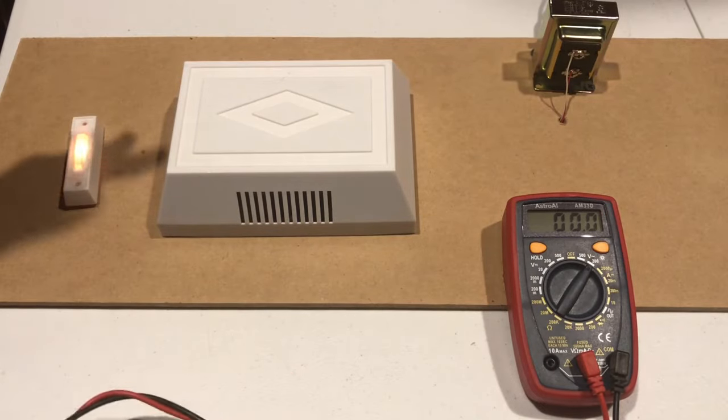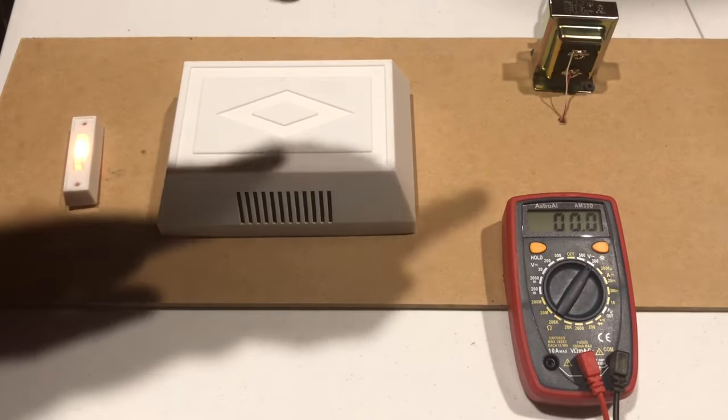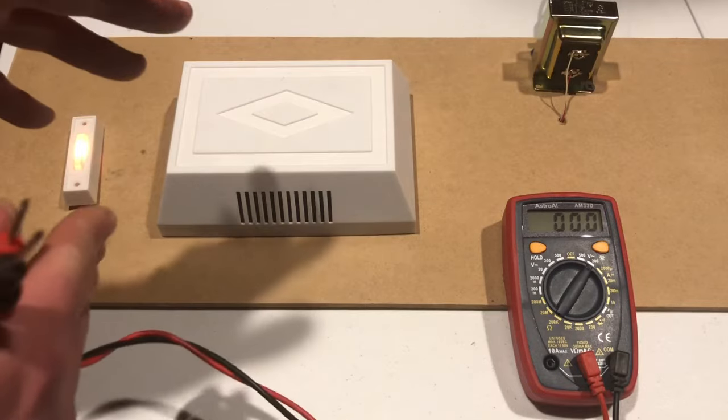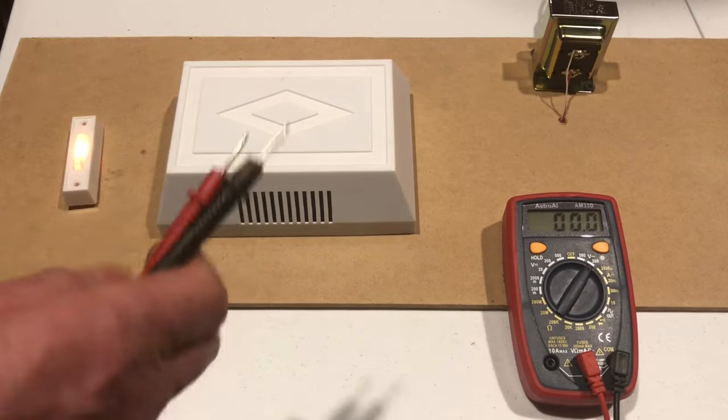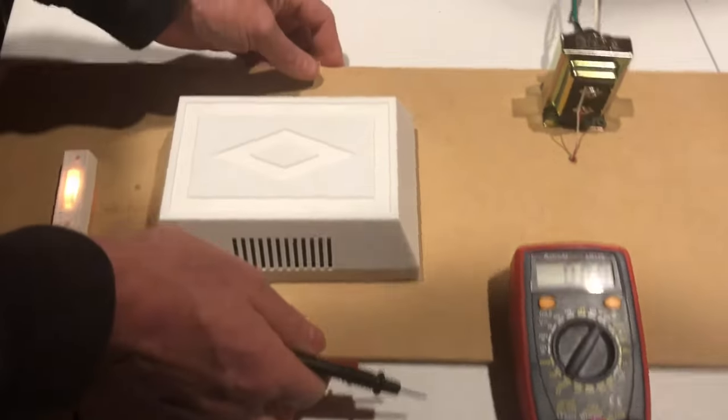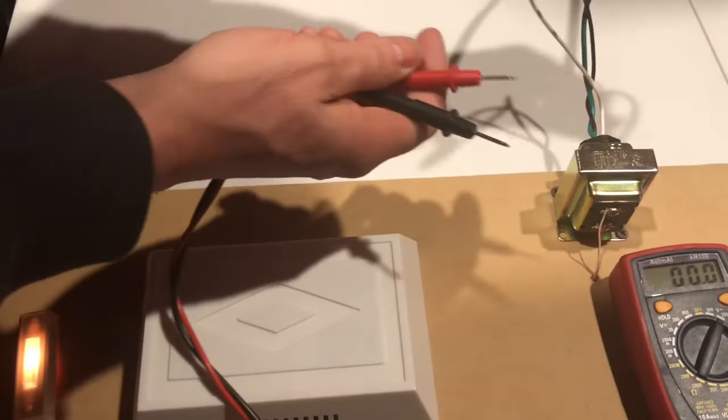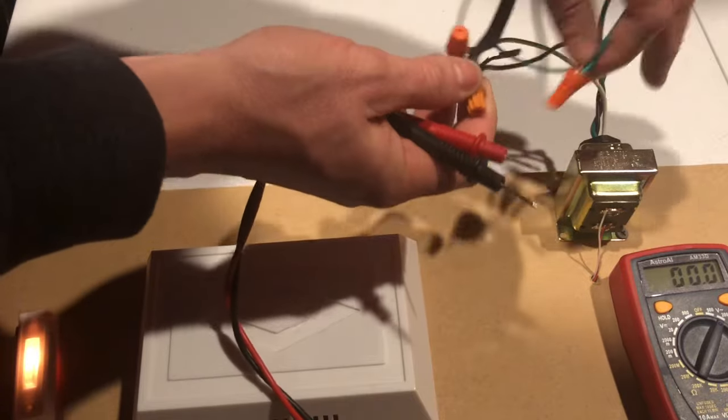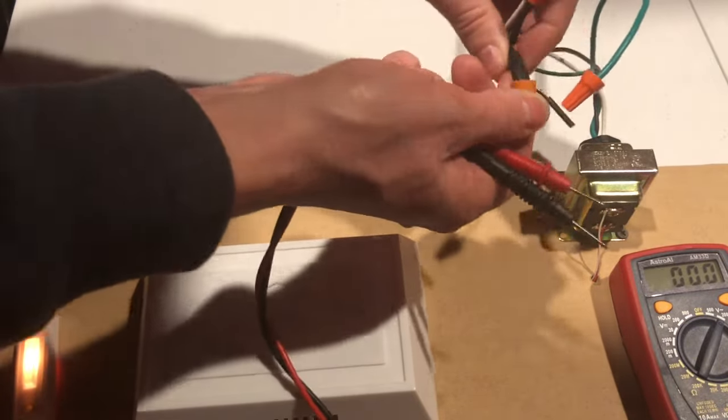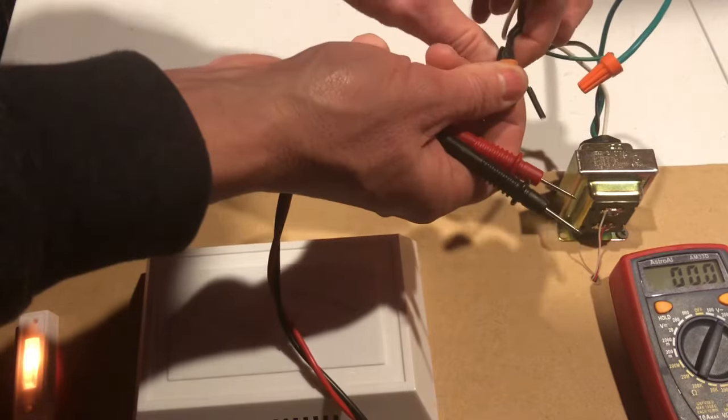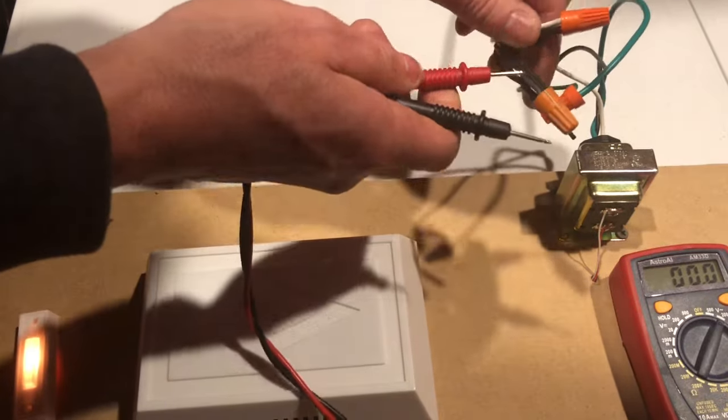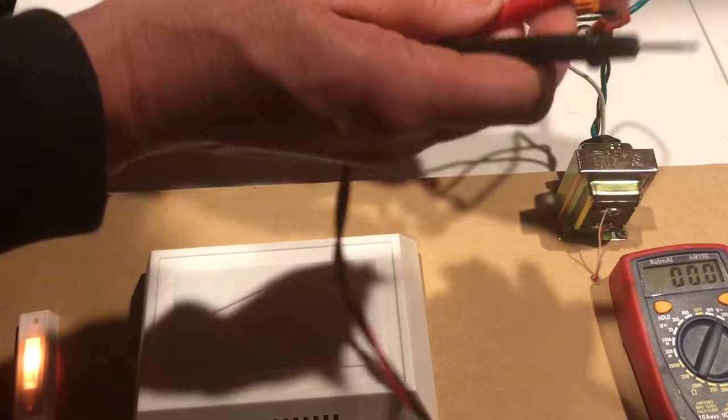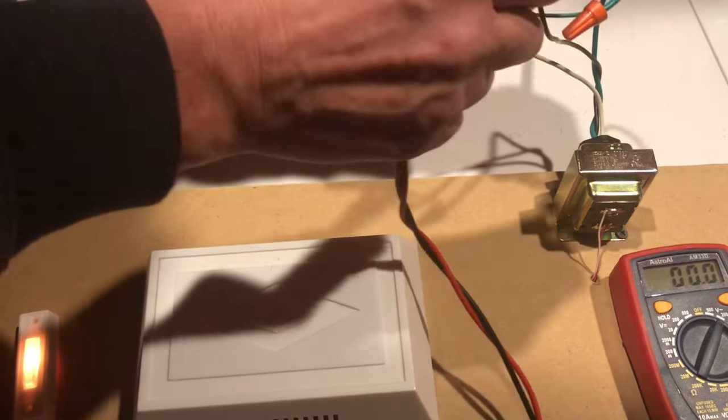Then we know that we've got a power issue going to the transformer or the transformer is bad itself. And so how we're going to test that is we're going to test the power coming to the transformer. So green is ground, white is neutral, and black is line voltage, or it's the hot side. So I'm going to stick my test lead in the wire nut.